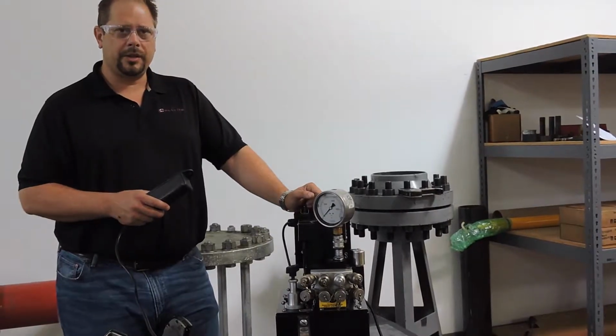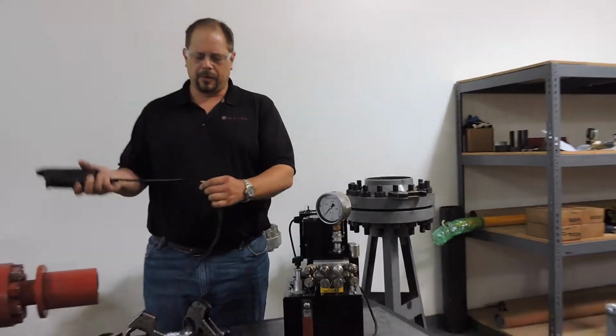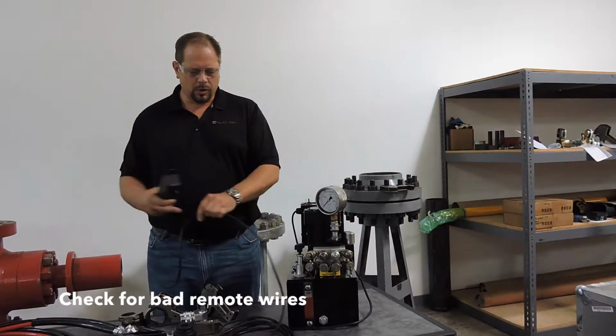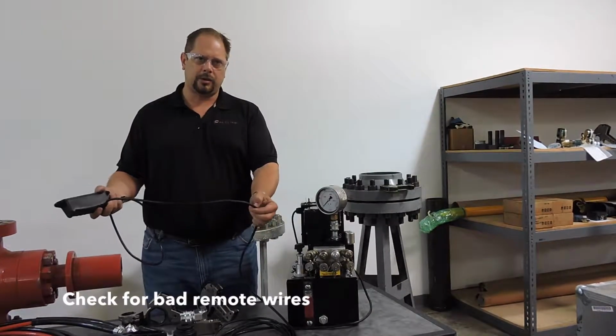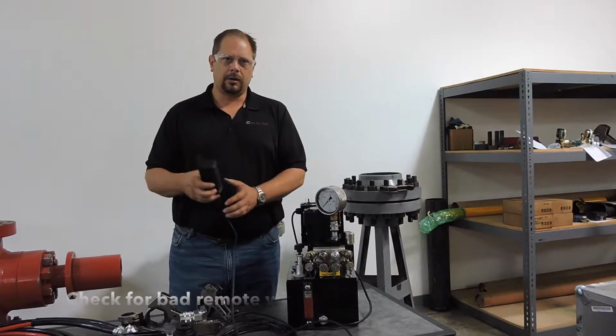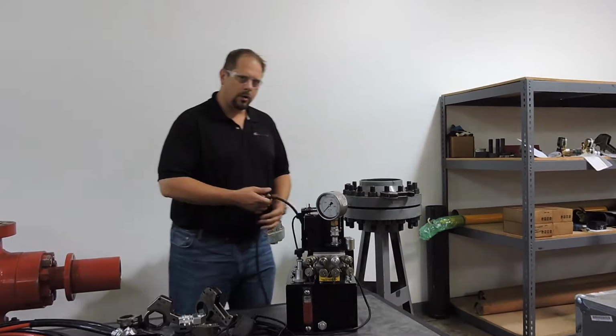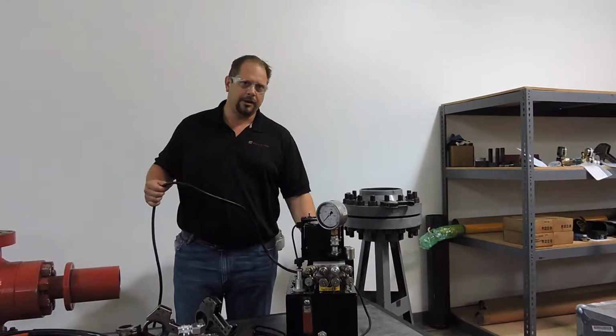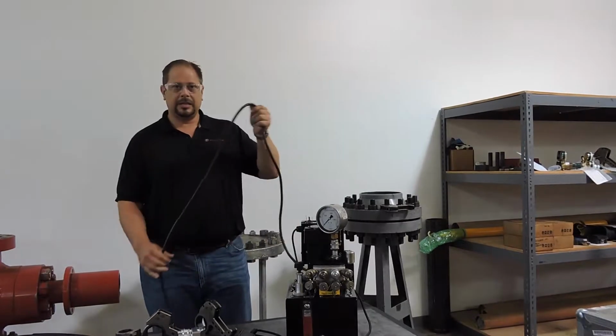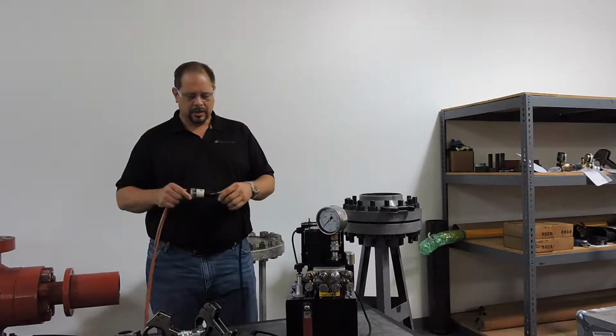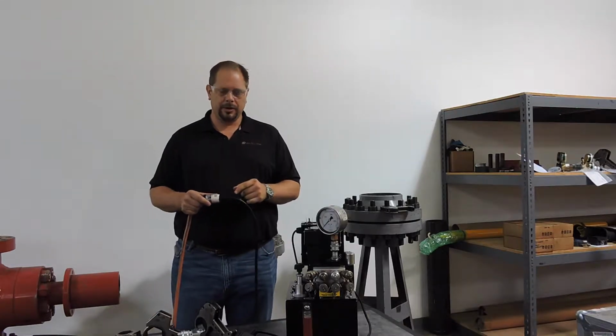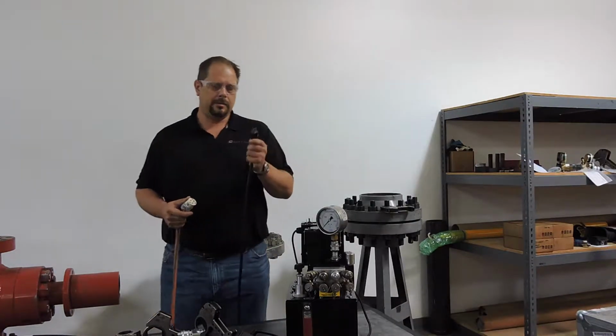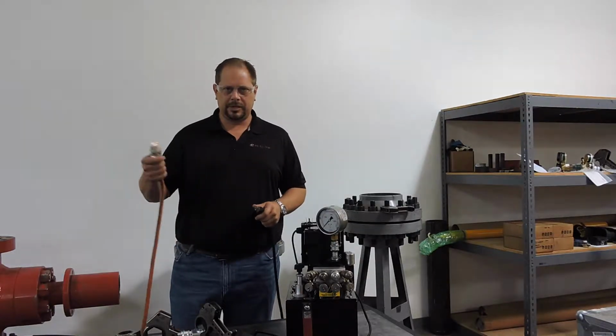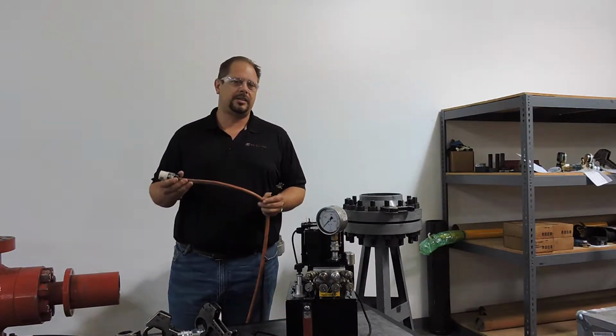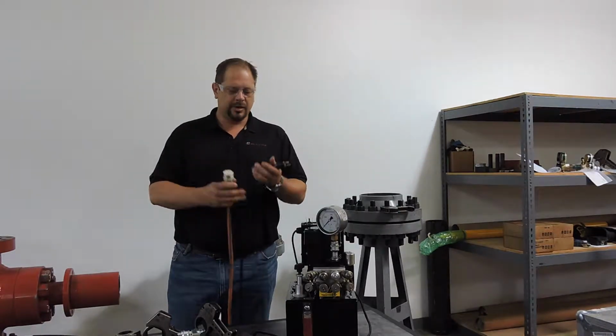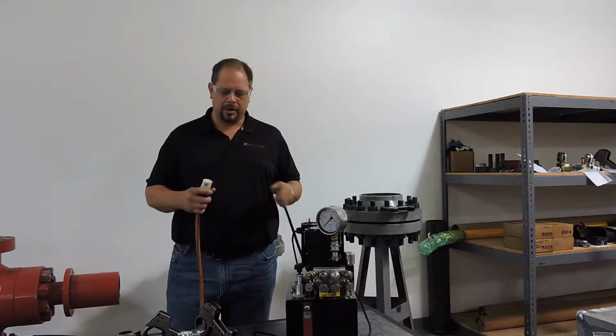Before you even get started with any of this, you need to make sure that all your cords are not frayed or bent or cracked. And if you just go and inspect these things looking for cracks and kinks or exposed wires, it will keep electrical hazards away. The power cord that's on the back of this should be securely fitted underneath the electrical box in the back. Make sure that it's not cut or has abrasions in any way, that the plug is attached firmly to it. And if you cannot plug this power cord into the wall directly and you have to use an extension cord, make sure you use the shortest, fattest extension cord that you possibly can. Make sure it is of equal size or larger than the one that's connected to the pump when you plug it in.